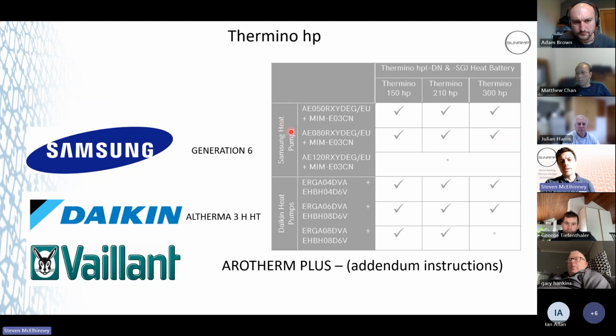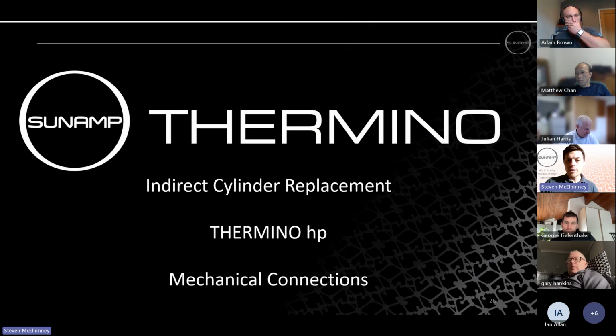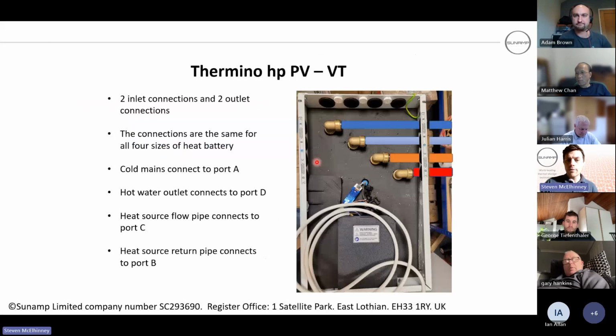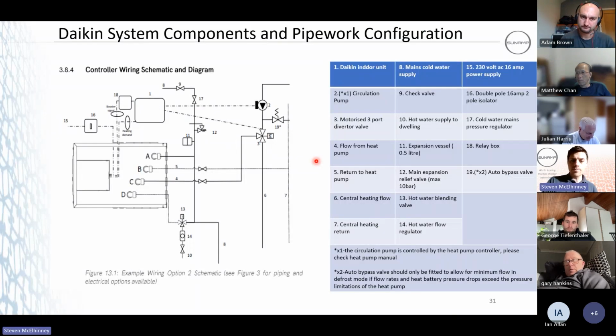Samsung 12, yeah. 12 kilowatt, because we start going higher than that for your flow rates. A lot of that flow is going round about your bypass, and not a lot of it's getting put into the battery itself. So I think for a 12 kilowatt, what you have is about 27 litres per minute, something like 27, 30. But it's just something to bear in mind.